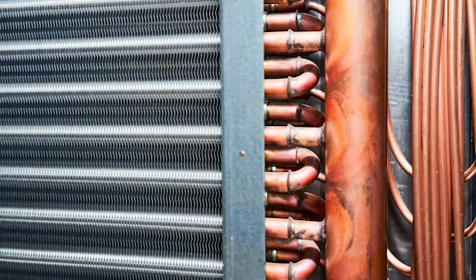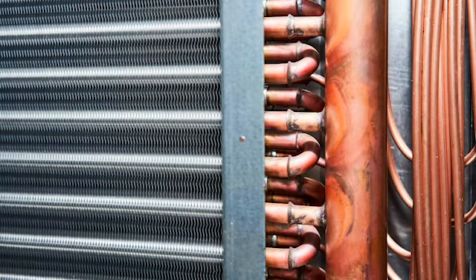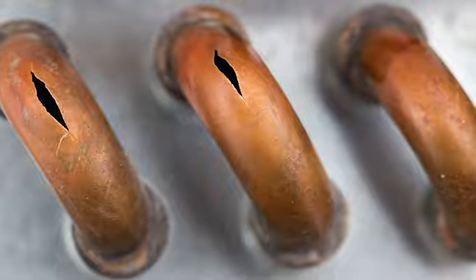What are the most critical HVAC maintenance tasks facilities should prioritize to ensure systems run efficiently through the winter months? Well, for us, our cooling coils are all water-filled coils, so we typically drain our coils in the fall. Make sure the water is out of those coils so they don't freeze and burst. And the same thing goes with our cooling towers. We drain those, clean them, get them in a dry layup for the winter months.